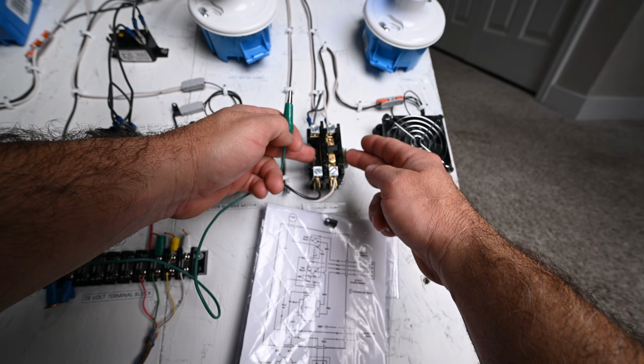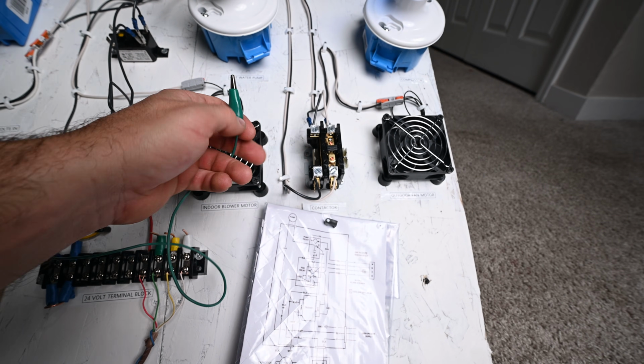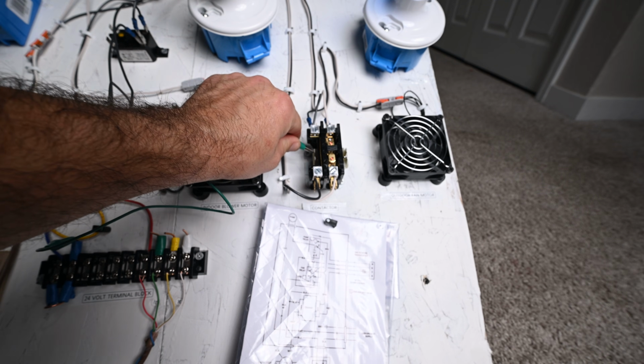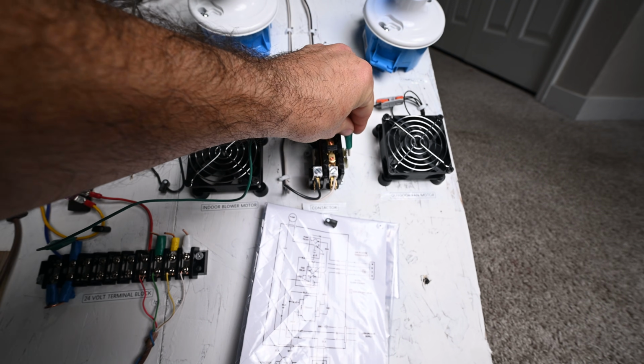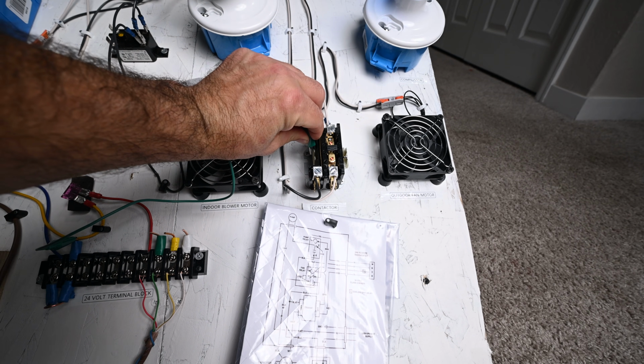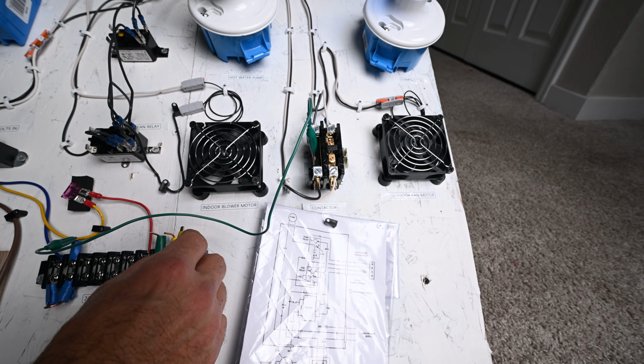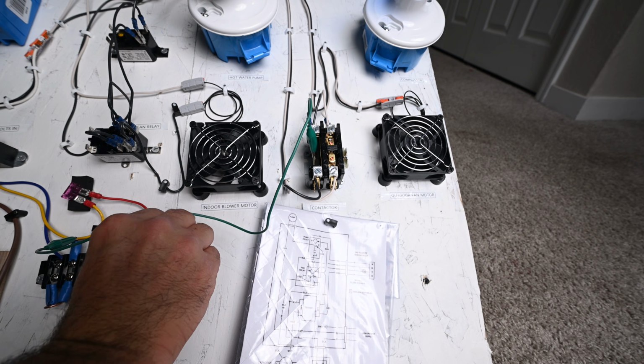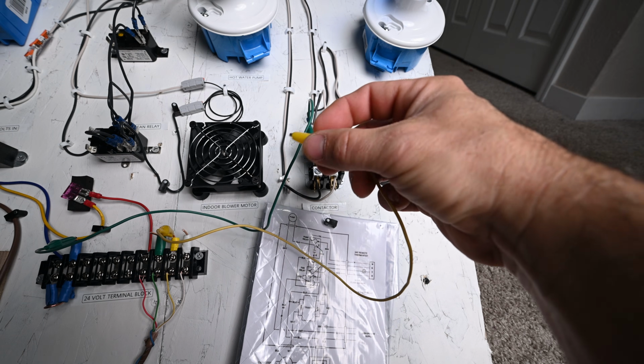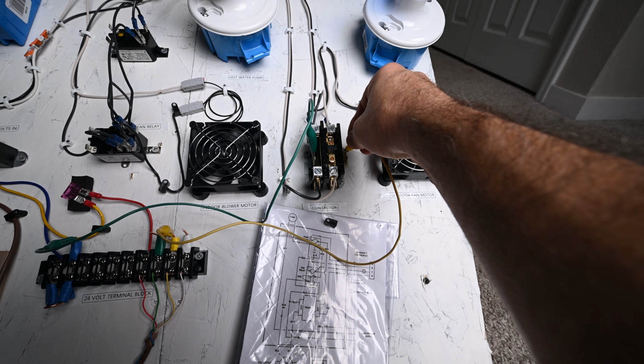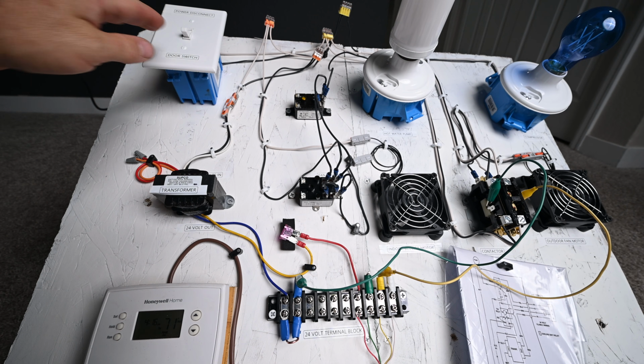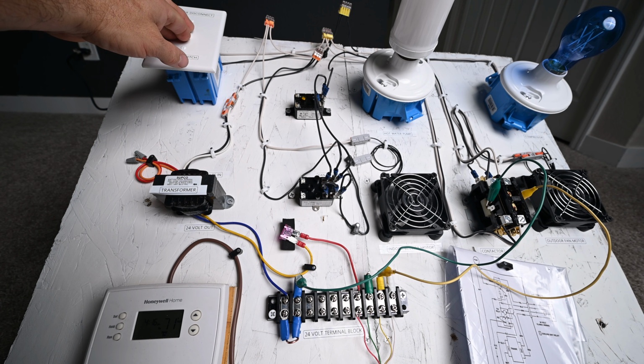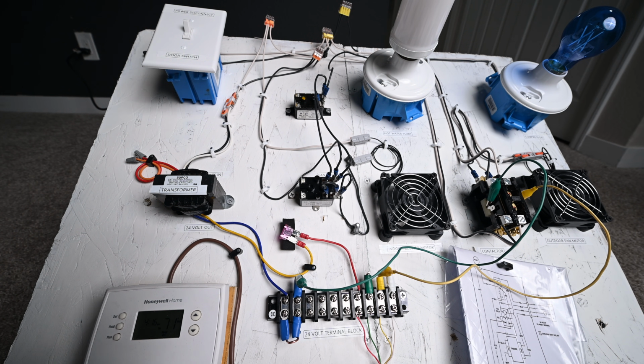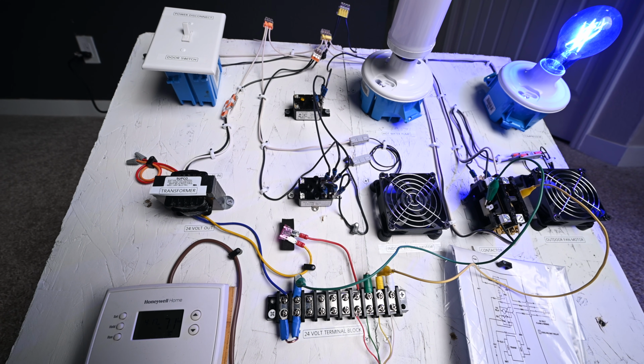That's this on the side. And if you look underneath the contactor, you can actually see the coil. I can put it on this side or this side. It does not matter which side it goes on. Now I'm going to hook up a jumper to the Y, to the yellow terminal block. From the terminal block, I'm going to go to the other side of the cooling contactor. Now I'm going to turn the power on, high voltage, to the test board. Nothing's happening yet because the thermostat is set for heat. So I'm going to turn it to cool. And we're getting a call for cool immediately from the thermostat.